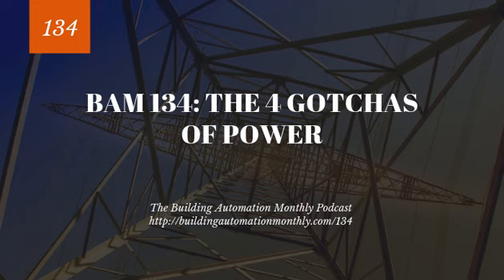Long story short, they were trying to illustrate that the common is shared between the power source and the controller, and that when you run from the sensor back to the common on the controller input, that input common is internally shared with the common on the transformer. If you're confused already just hearing that, we've got an issue, because a lot of folks are.